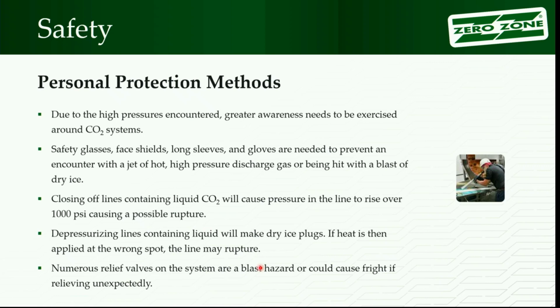When you drop that liquid down inside a pipe below 100 pounds pressure, 60 the actual number, it will instantly convert that liquid into dry ice. So depending on what you're doing, where you drop the pressure down, you could potentially get a plug of dry ice in a liquid line. Then you've got to wait for it to kind of warm up and melt. So it's something just to be aware of, which you have to work with.